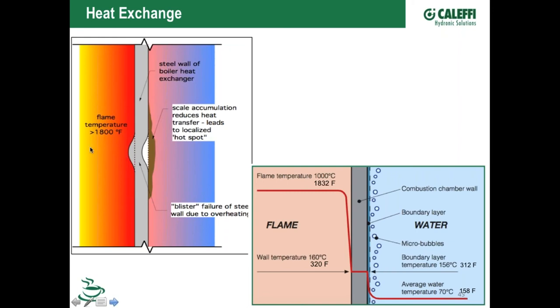So what happens is when this heat's trying to get through to this water, you've actually put a bit of an insulation layer in there, and that's where you're going to overheat that metal. That's where when you see a boiler with a pinhole in it, if you were to take a bandsaw and cut that in half, you'd probably see a big scale buildup on the other side of it.